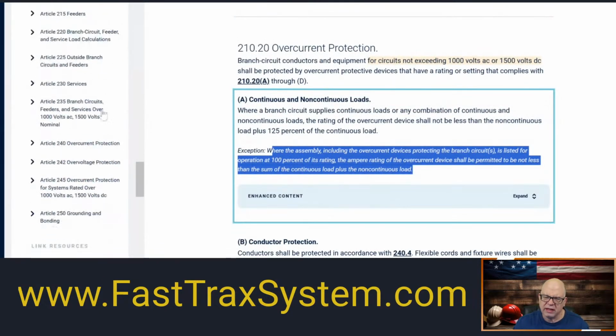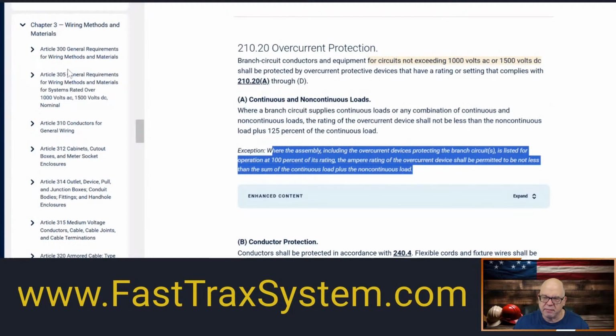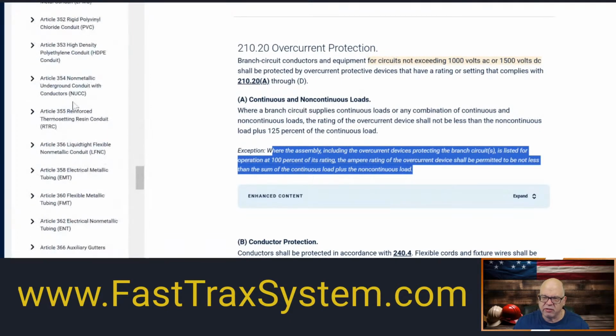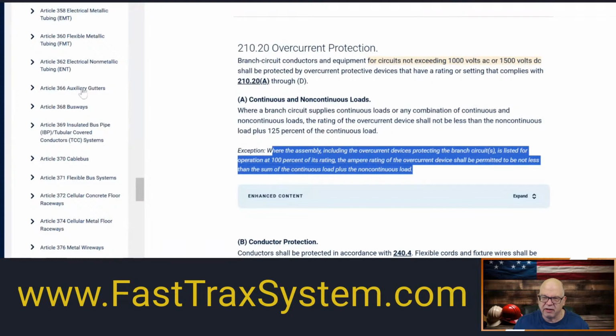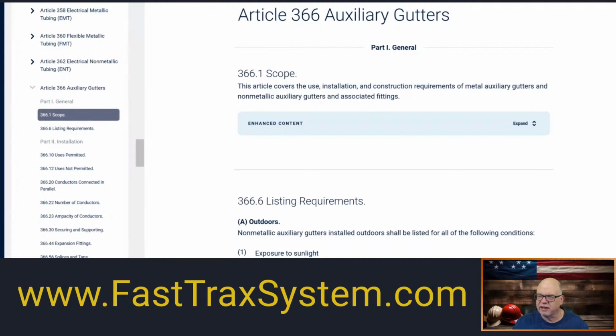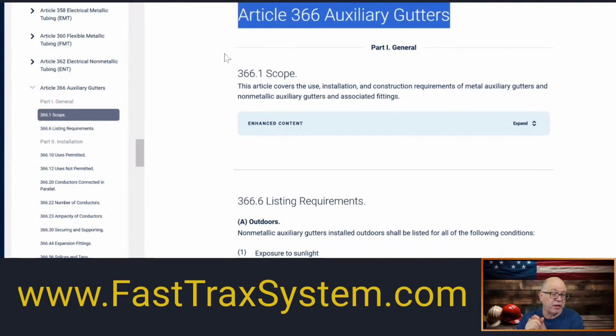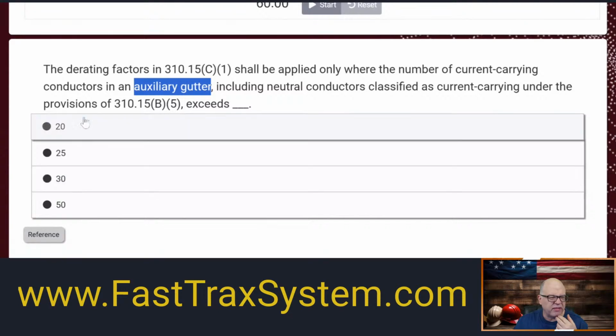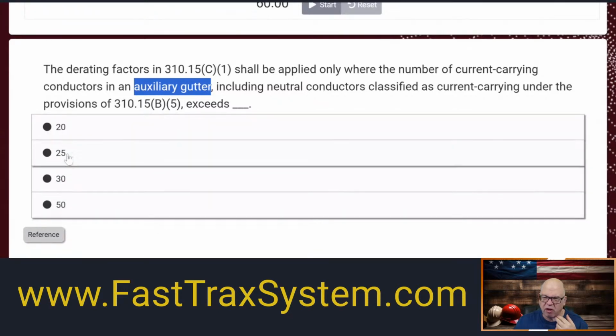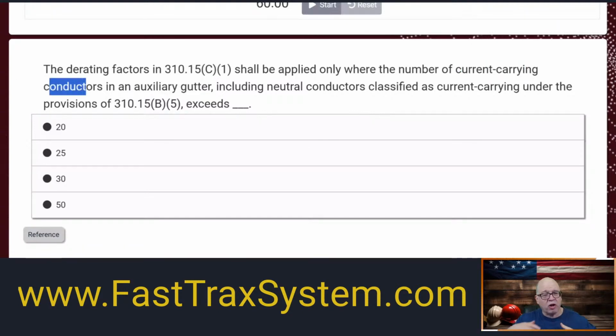So we know in our training that this is going to be the wiring method, and it's going to be here in chapter 3, auxiliary gutters in 366. Okay, so I'm in auxiliary gutters right here, and I'm going to bold scan. And remember from the question, I'm looking at current carrying conductors. I'm looking for other references that I can remember, for example these numbers, 20, 25, 30, 50, and terms like current carrying conductors. I'm using all these terms as I'm bold scanning for something to trigger me to stop. That's what I'm doing.